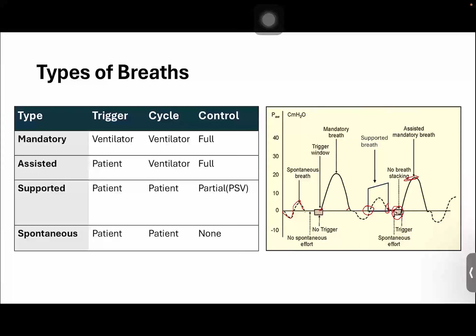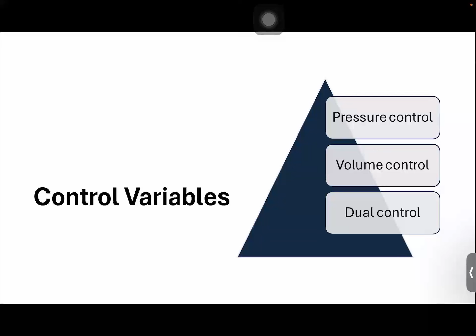Then we talk about the control variables, the main thing which is controlled during the inspiratory phase. That can be pressure control, volume control, or even dual control, like pressure regulated volume control or volume targeted pressure control. Two main entities: first, volume control ventilation, where we set a definite tidal volume. The ventilator delivers a constant flow to achieve that set tidal volume. The expiratory phase is passive anyway. So it achieves a certain peak inflation pressure or plateau pressure.